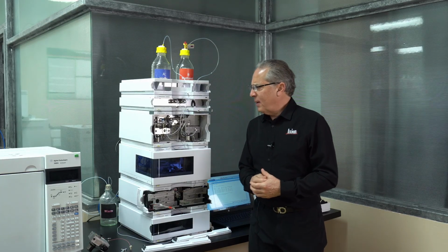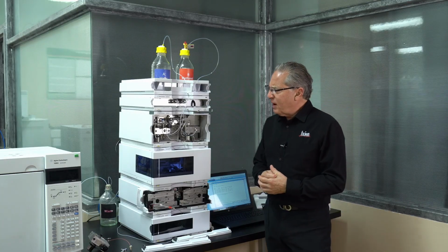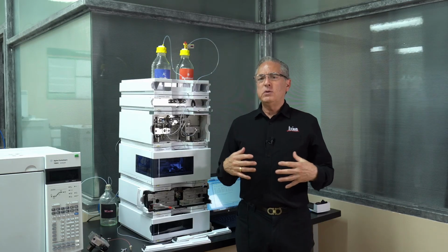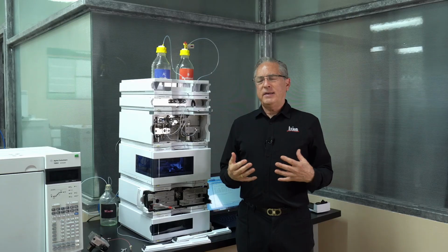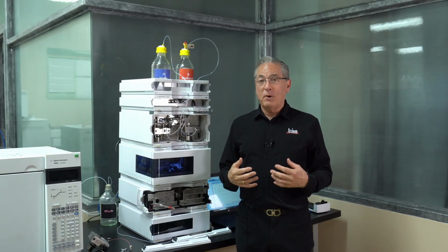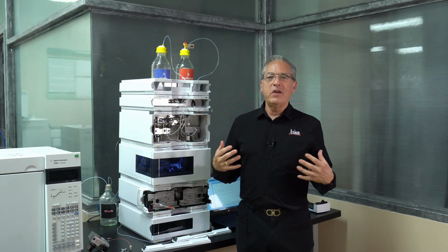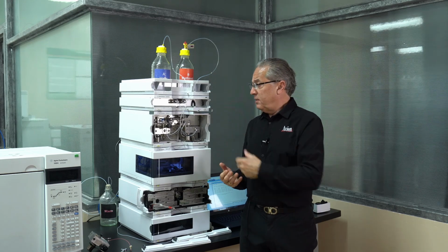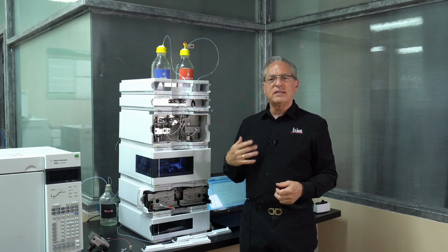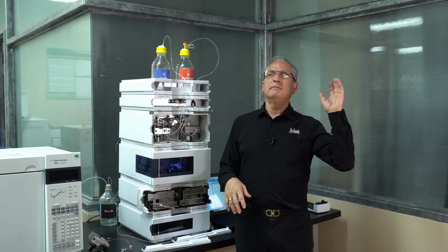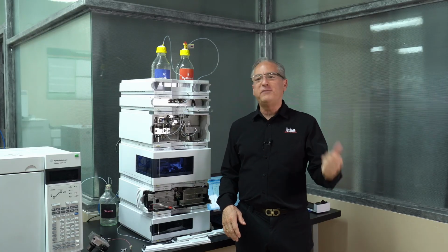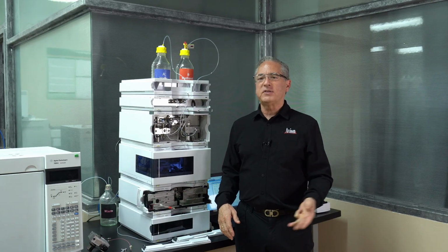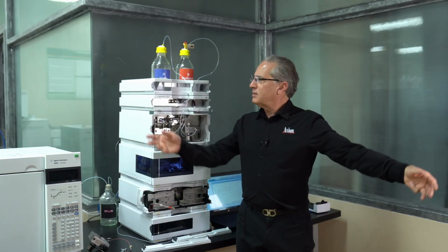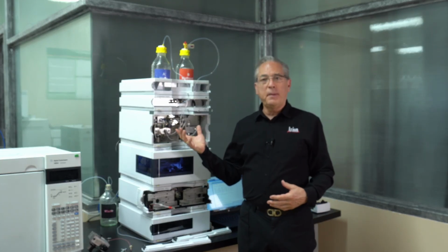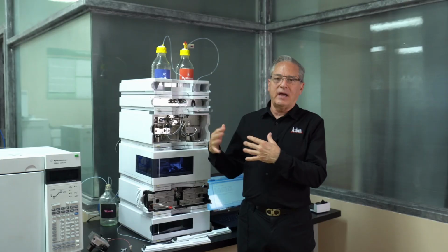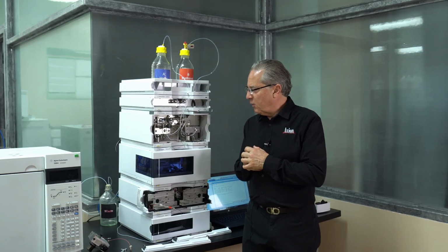So in changing the pump seals, just about every HPLC instrument in the world uses the same procedure, but there's a little different way to get to them. But once you get to the pump seals, to me, it's all the same. So I'll show you how to do it on this design. The Agilent design is the same all the way back to the late 80s. We went from the 1050 to the 1100, the 1200, the 1260s. I got the 1260 Infinities, got the Infinity 2s. They all have the exact same pump heads, and you'll see this common design across all different folks out there.